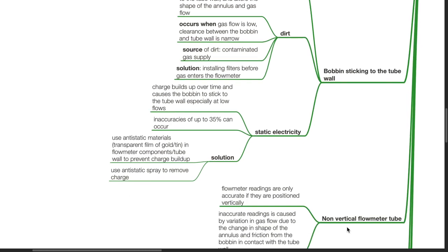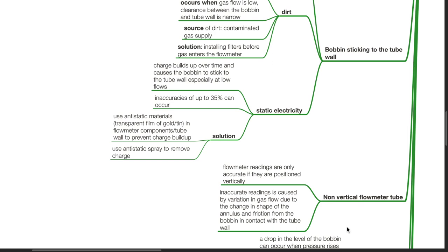Static electricity: Charge builds up over time and causes the bobbin to stick to the tube wall especially at low flows. Inaccuracies of up to 35% can occur.